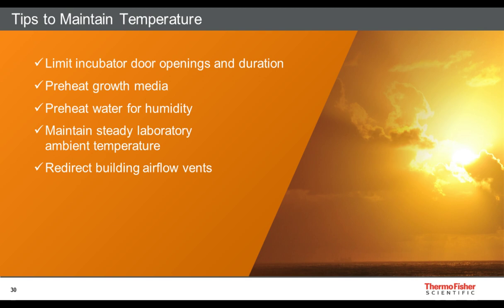Often, even in clean rooms, I walk in and see building air ducts for heating and cooling in the ceiling or on the wall, pointed right at the incubator. Those blowing intermittent cold or hot air on the incubator will change what the incubator is experiencing and how it has to heat the cells. So one thing to do is use a passive air duct diverter to change that airflow so it's not blowing directly on the incubator.